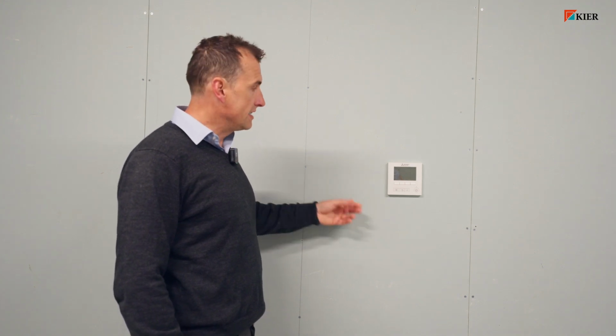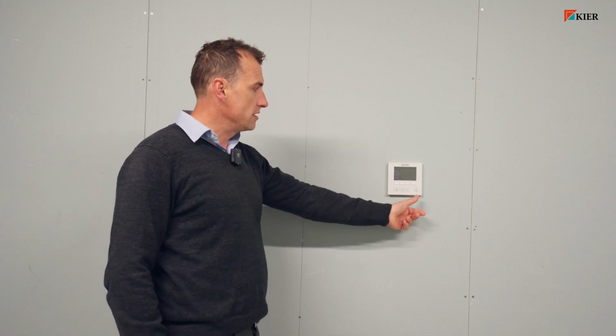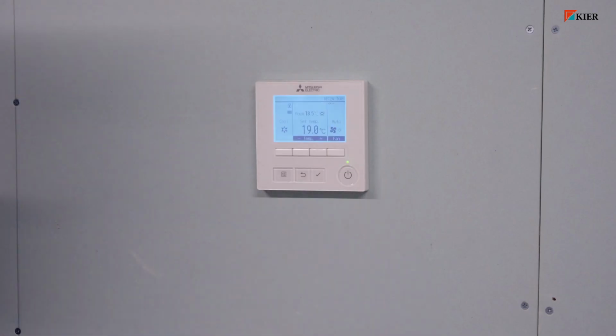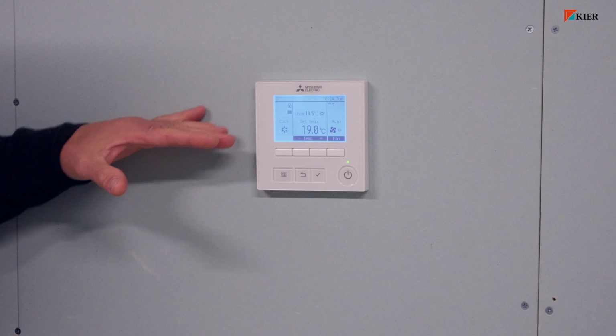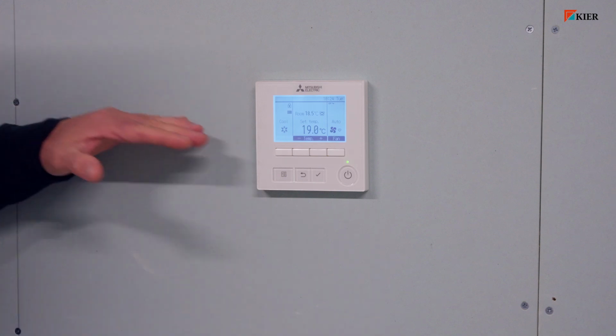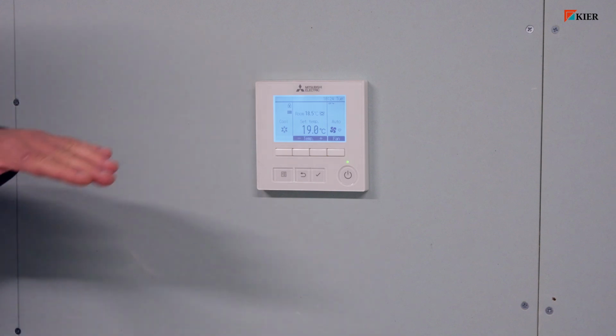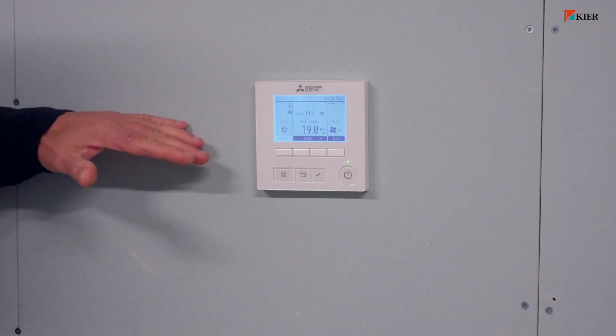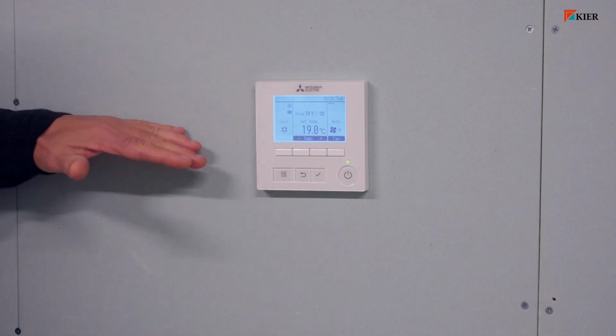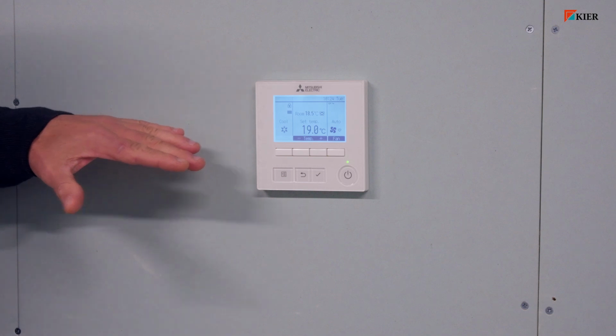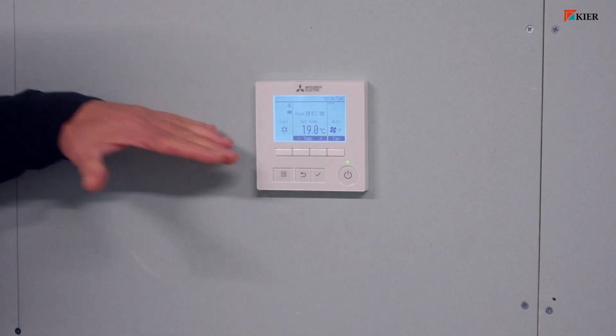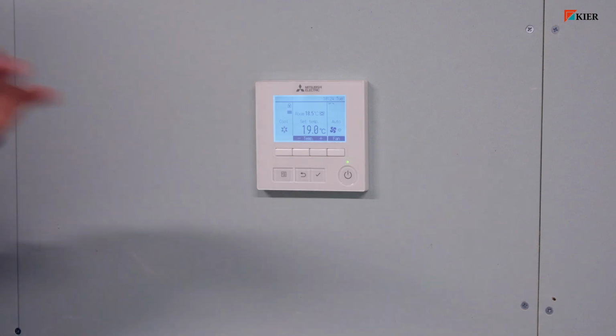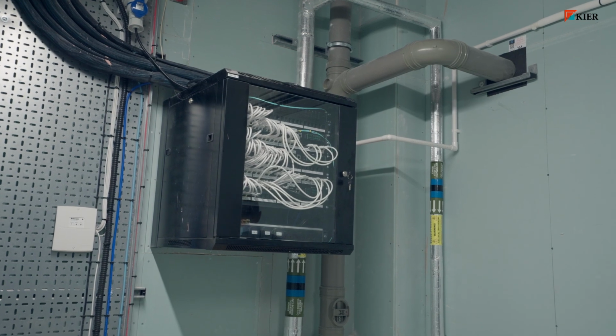This demo is the comms room AC units. So in order to activate the unit, you just press this on button. The temperatures are set at 19 degrees for cooling. We have also inserted a lock facility, so at the moment these systems are locked on cooling only, so they cannot be inadvertently changed to heating. And this is obviously to keep this area cool so that the equipment behind me stays in a cool condition.